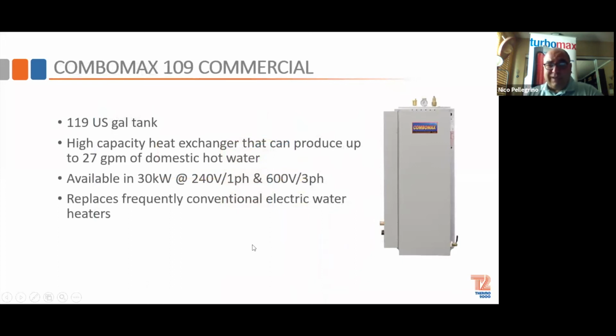We also have a commercial version, and that one goes up to 30 kW, and it's also available in 600 volt three-phase. We've done a couple of projects with Ryan, again, with eye wash stations in factories, where this is right there, right beside the eye wash, and we actually meet their standard that they need. You need so many GPMs at so much time at so much temperature with this tank. So we've had some success with that in that situation.